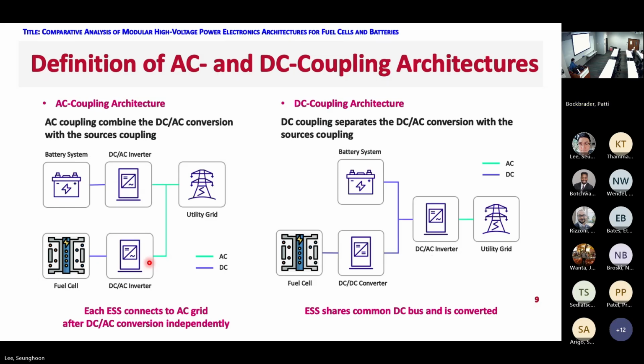On the right, the DC coupling architecture first combines the ESS units into a common DC bus before using a single DC to AC inverter to interface with the grid. In this configuration, the sources are coordinated at the DC level, and only one AC conversion stage is required. This generally improves overall efficiency and enables more optimized energy management between the battery and fuel cell. In summary, AC coupling provides simplicity and independence, while DC coupling offers higher efficiency and better integrated control.